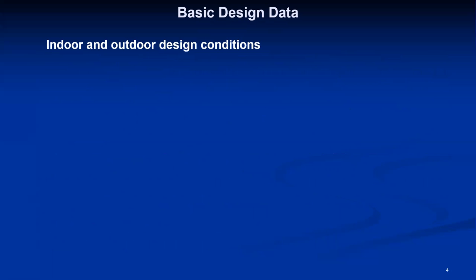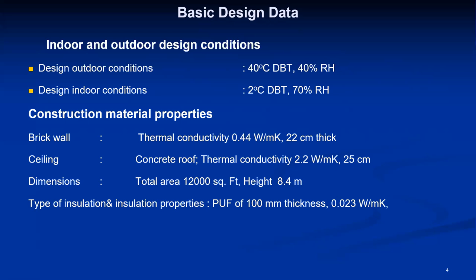The basic design data for this cold storage is given. Outdoor design conditions are considered as 40 degrees Celsius DBT and 40% RH. Indoor design conditions are based on the product to be stored. In this sample case, onion is the product, so the recommended indoor conditions are 2 degrees Celsius DBT and 70% RH. Construction material properties are given: a brick wall with thermal conductivity and thickness, and a concrete roof with its thermal conductivity and thickness. The total area available is 12,000 square feet and the recommended height is 8.4 meters.